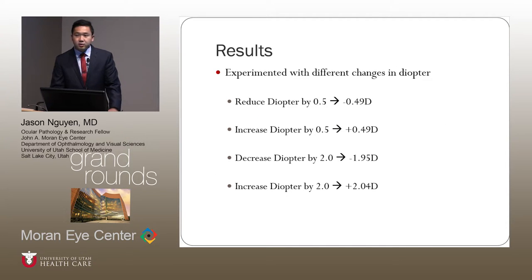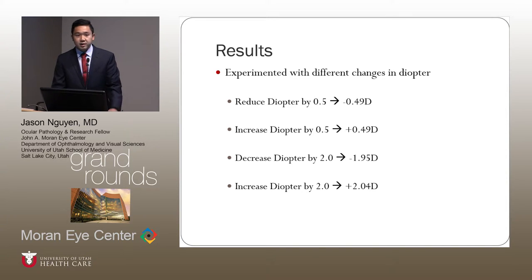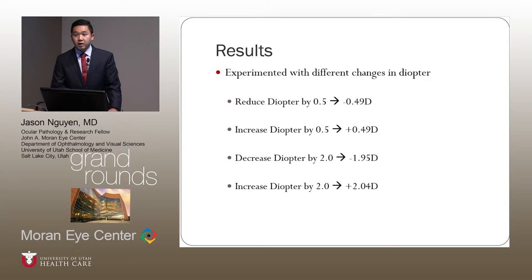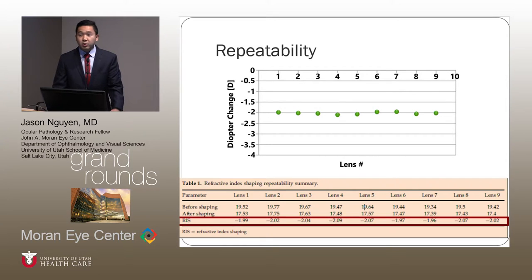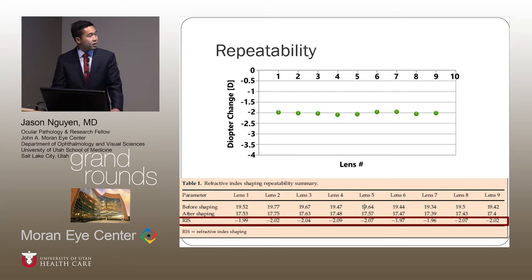This next slide summarizes the results. The company experimented with both reduction and increase in diopter, and with different increments, they got very close to all their targets. They then experimented with nine different IOLs to assess how repeatable it was. As you can see in both the chart and the table, not only is the process very repeatable, but it's very accurate.